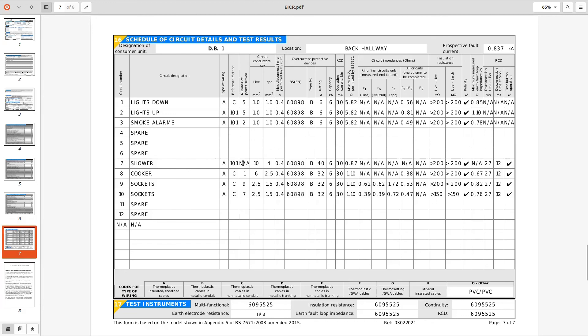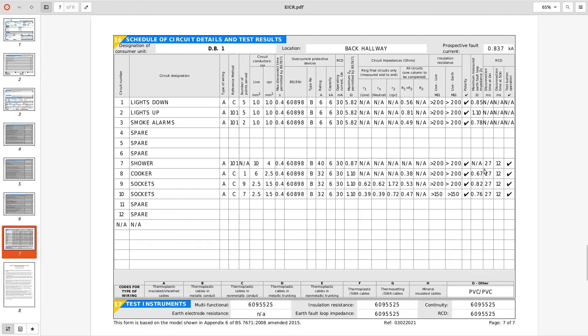No point served for a shower disconnected, perhaps possibly a disconnected shower circuit there has not got any R1 R2 readings for some reason. Again maximum Zs values are wrong for all these, they should be 95 percent of 1.15 whatever that calculates to be, I'm not going to do in my head. Again calculated Zs is on the end, we've got RCD times so we have got RCD protection I presume by this is 30 milliampers, put 30 somewhere here interesting. So yeah that's the test results.